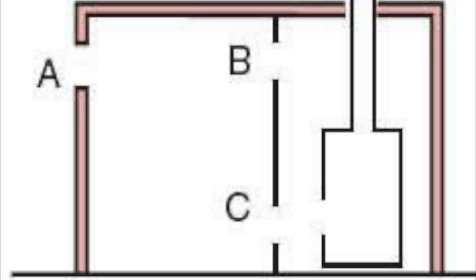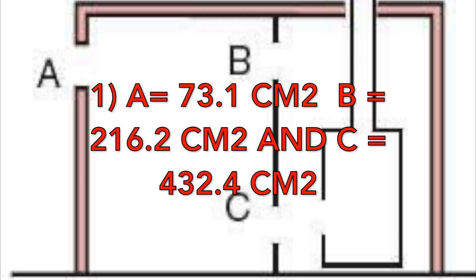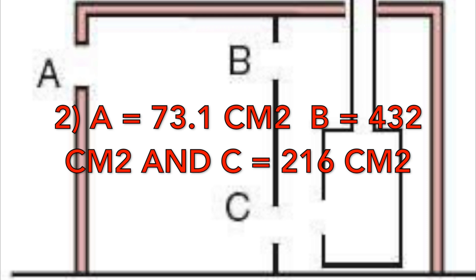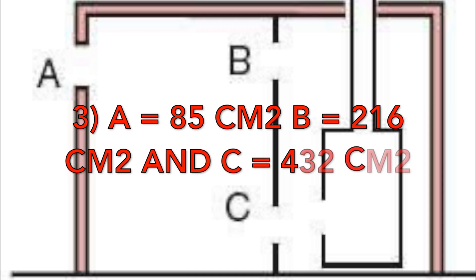The final question, number ten: we have a 24 kilowatt gross open flue boiler installed in a compartment which gets its air for combustion via another room. What ventilation is required at A, B, and C? Is it 1) A=73.1, B=216, C=432; 2) A=73.1, B=432, C=216; or 3) A=85, B=216, C=432?